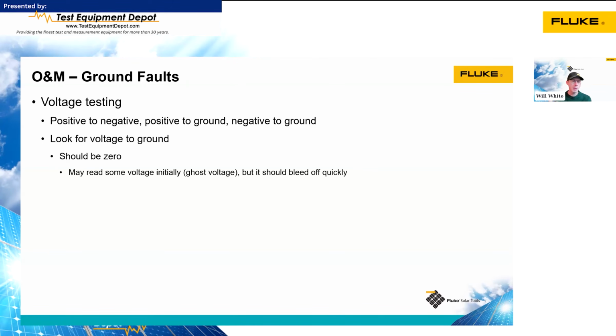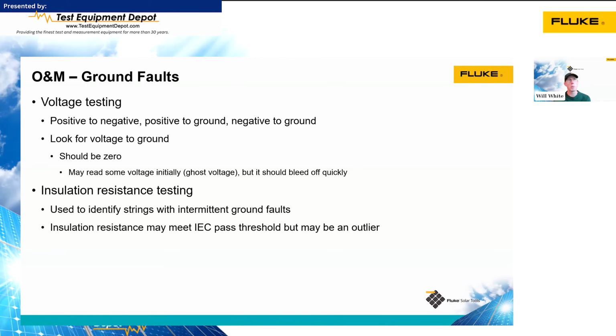When I'm doing that testing, a lot of times we'll see some voltage show up at first, and then it will slowly trickle down to pretty close to 0. That's just ghost voltage. It'll bleed off really quickly. If it stabilizes at a certain point, then we've got some real voltage there. We can also use insulation resistance testing. It's particularly helpful to find intermittent ground faults.